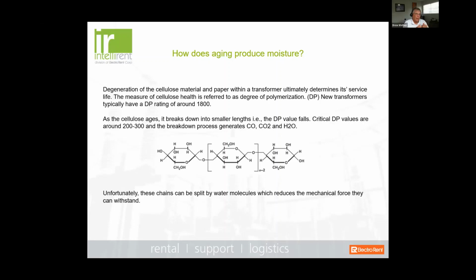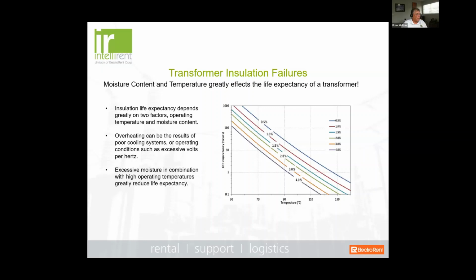But as these molecular bonds in the cellulose and the resin start to break down, the byproduct is moisture. So as the insulation starts to deteriorate over time, which again is caused by heat, oxygen, and moisture, of course, it's self-perpetuating. So what happens is we have no exposure at all to the air, okay, but we also can get a large ingress of moisture.